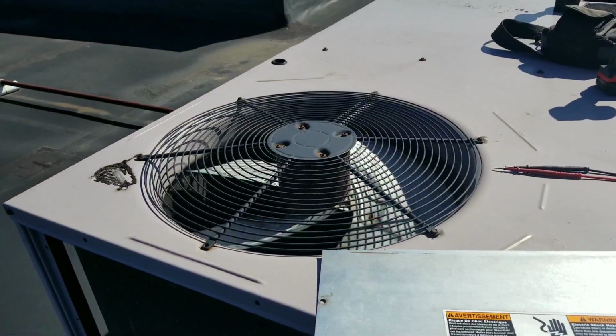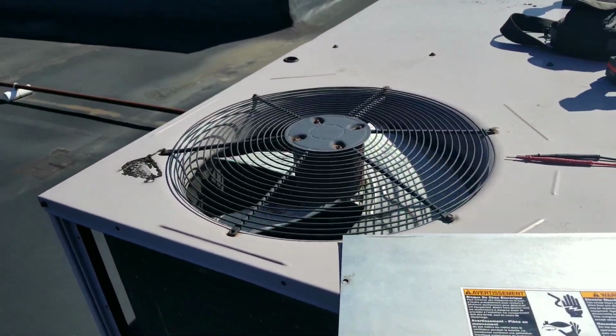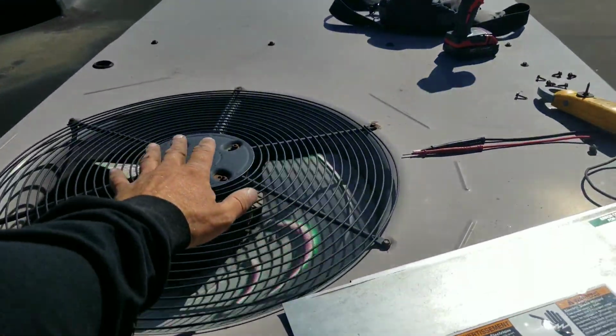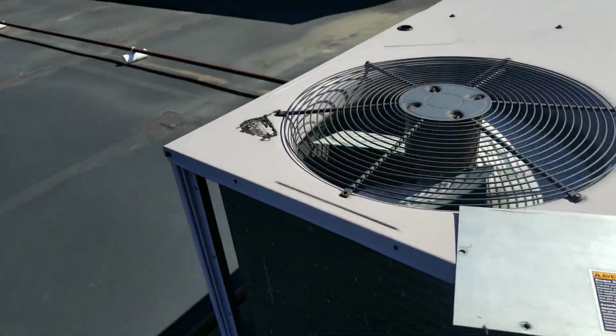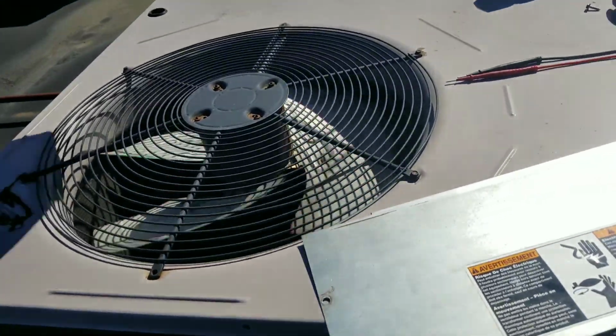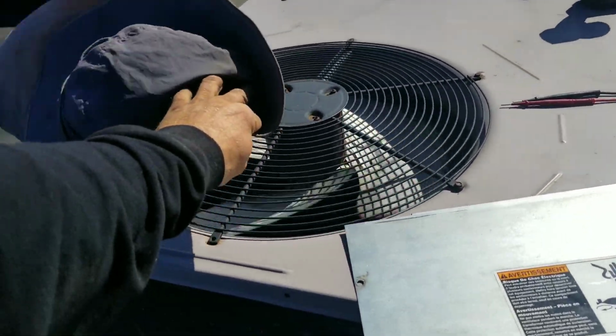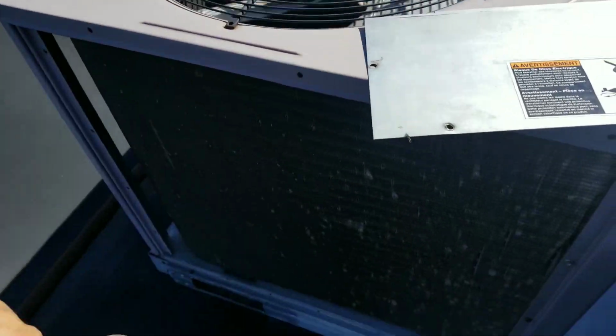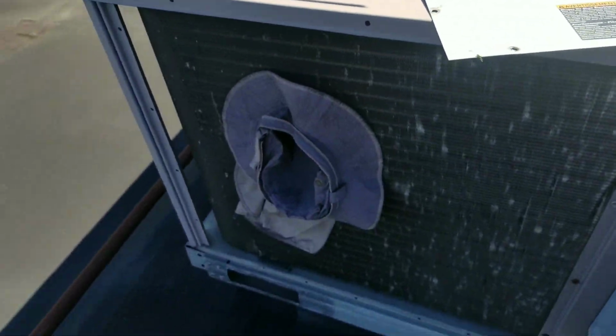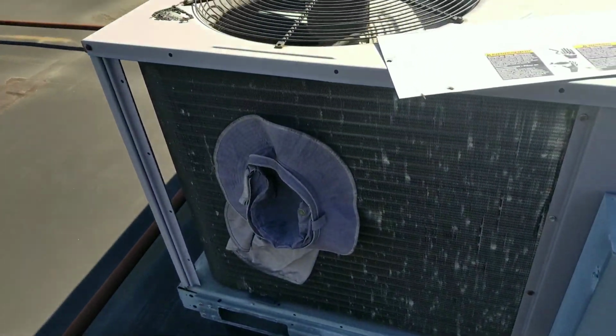I know it looks like the condensing motor either isn't spinning or is spinning very slowly, but it is actually spinning. Let's do the old air CFM test on her. See, it's working. That's about 200 CFMs right there.